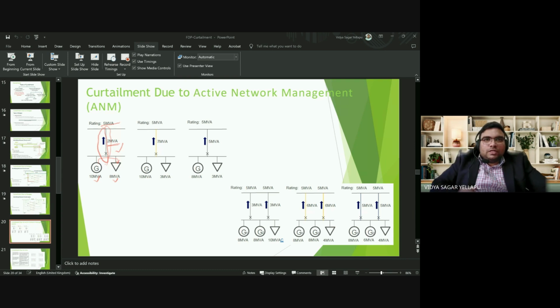However, if the demand of this load reduces to 3 MVA, in this case there is an excess power of 7 MVA. If that is exported to the upstream network or to the substation, then there will be a problem, because this circuit is only rated at 5 MVA and there is an excess power of 2 MVA. So in that case, the active network management system, the ANM system, sends a command to the generator to reduce its power output to such a value that this asset is not overloaded.